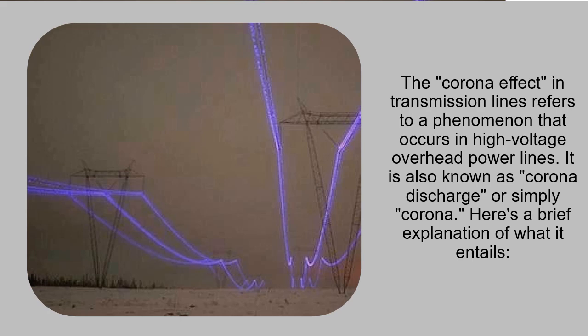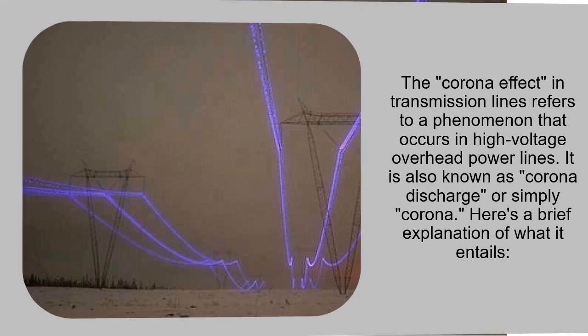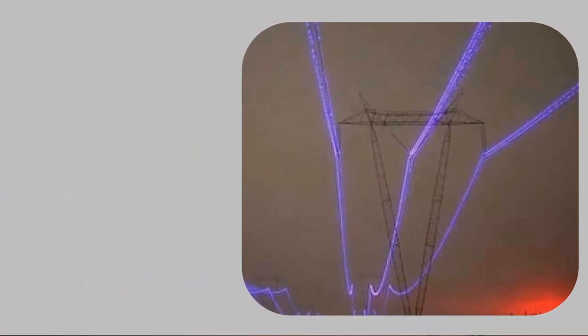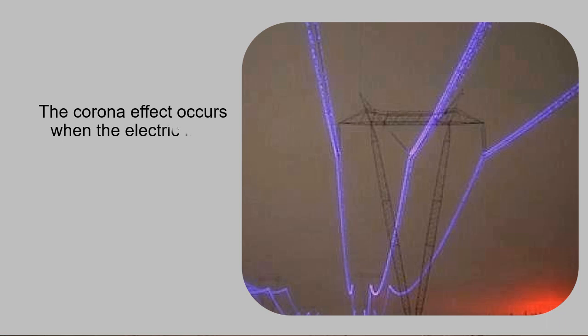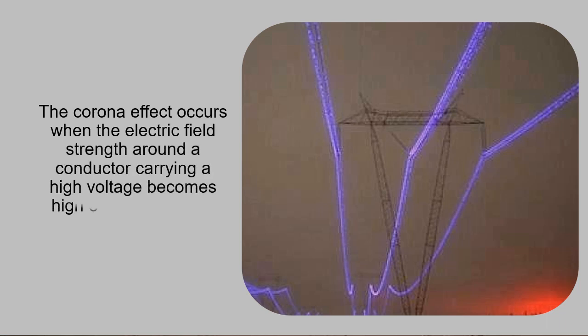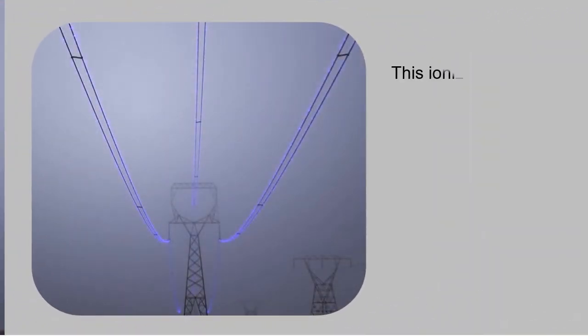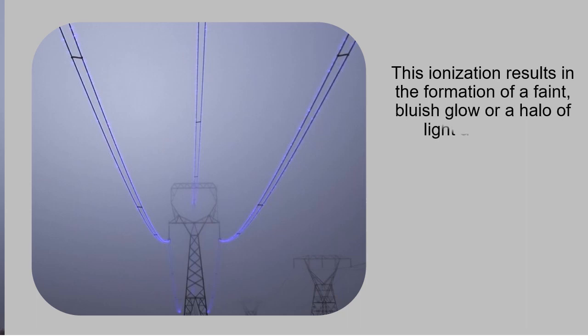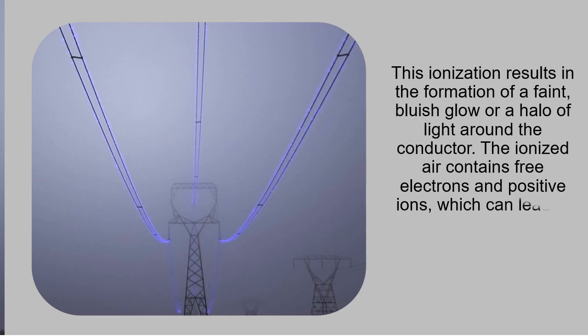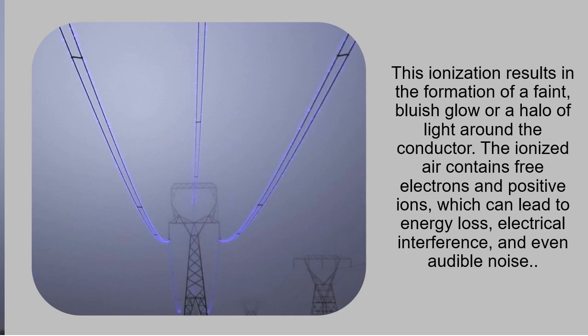Here is a brief explanation of what it entails. The corona effect occurs when the electric field strength around a conductor carrying a high voltage becomes high enough to ionize the surrounding air. This ionization results in the formation of a faint, bluish glow or a halo of light around the conductor. The ionized air contains free electrons and positive ions, which can lead to energy loss, electrical interference, and even audible noise.